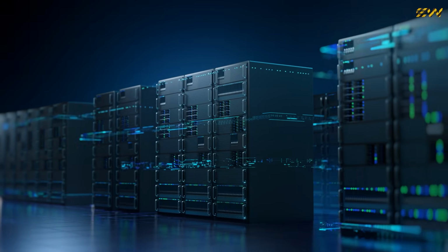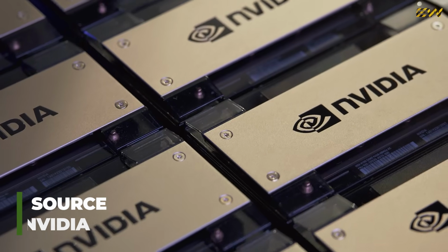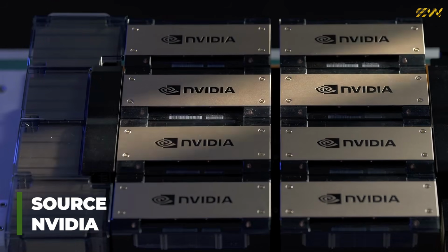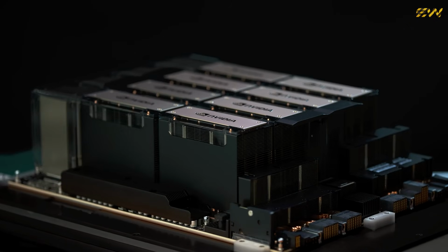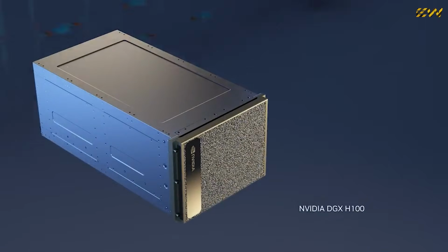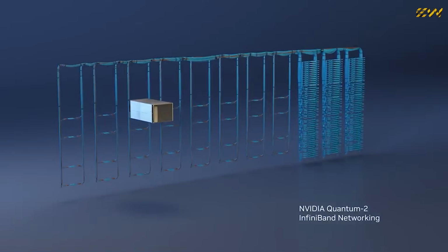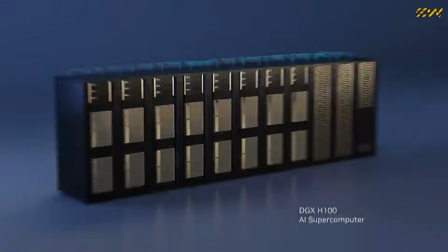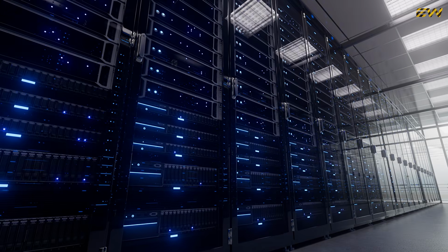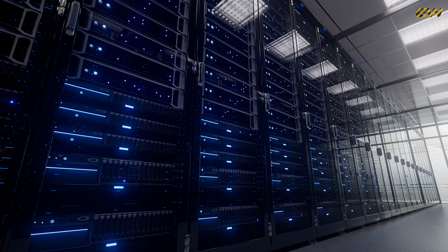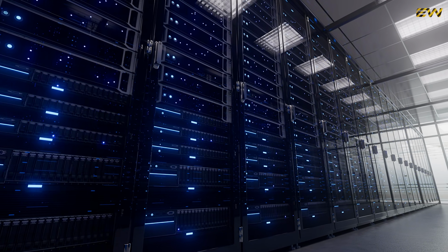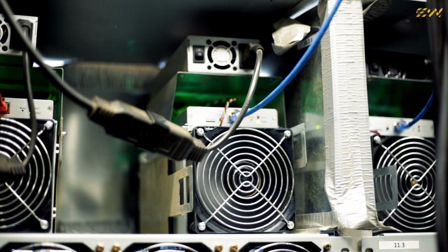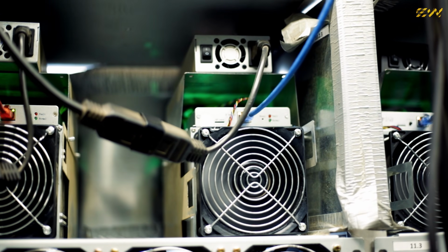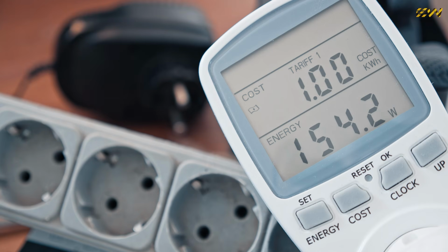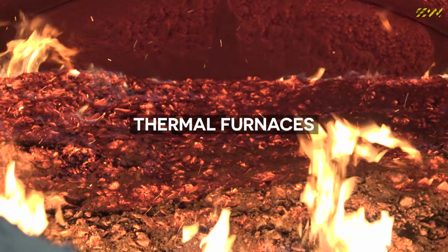Rack density explosion. Let's zoom in. A modern AI server using NVIDIA H100 GPUs can draw between 3 to 5 kilowatts per chassis. Now multiply that across a rack. Traditional racks handled 10 to 15 kilowatts. AI racks, 60, even 100 kilowatts. Some high-performance computing environments exceed that. That's nearly a tenfold increase in localized power density. And power density equals heat. Every watt consumed becomes heat, which means these facilities aren't just power hungry, they're thermal furnaces.